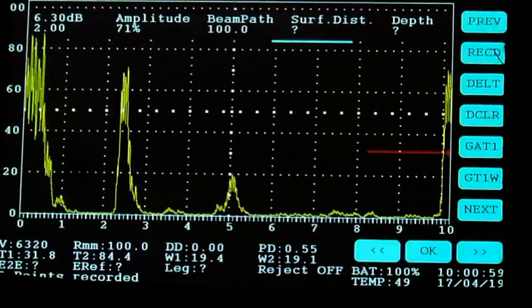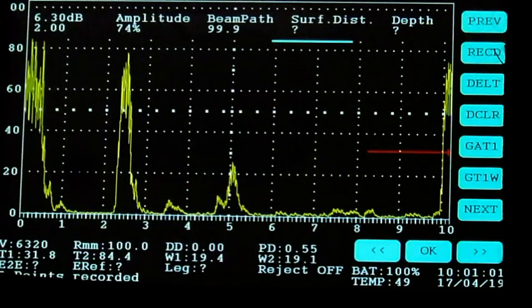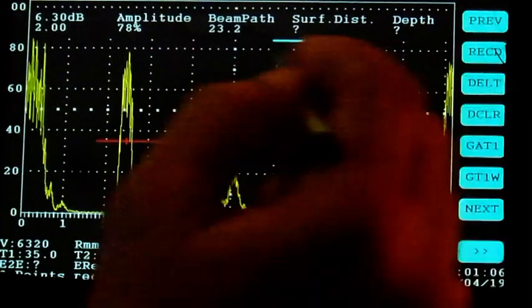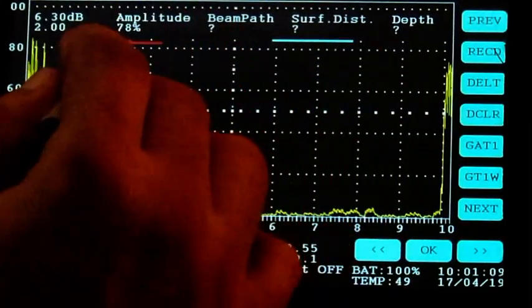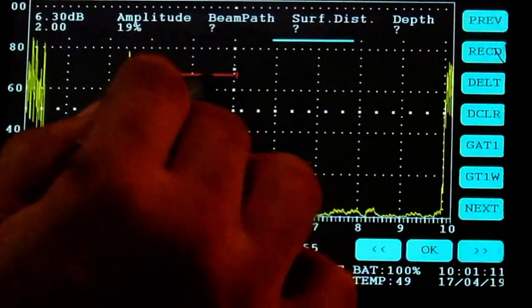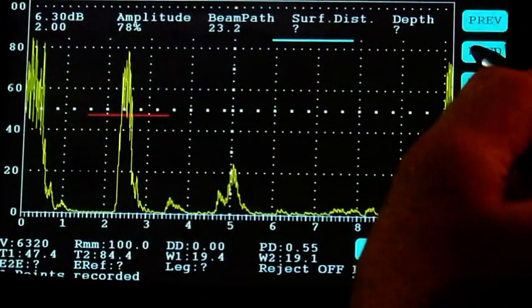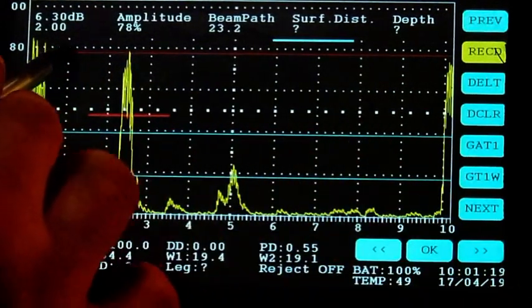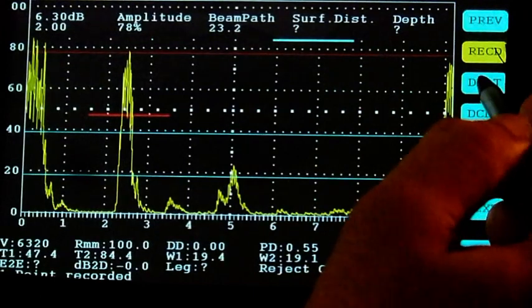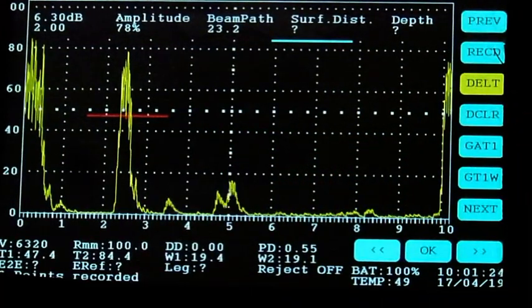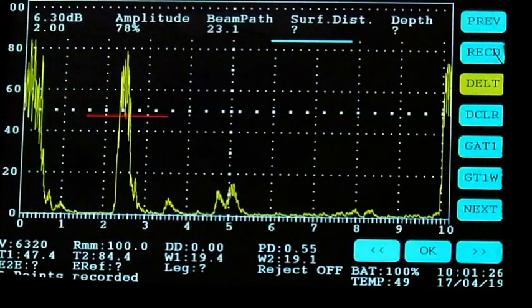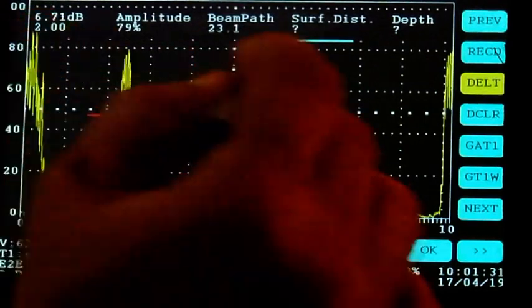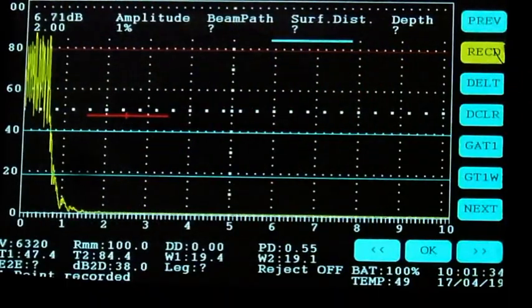This is the back wall that occurs at 100 millimeters. This is the first reflector indication which is actually gated, and then use the record function to record this point. That's the first point in the DAC, made slightly below 80%. If corrections are needed, then you may readjust, delete and readjust. Set it to 80%, so that's the first point being made.